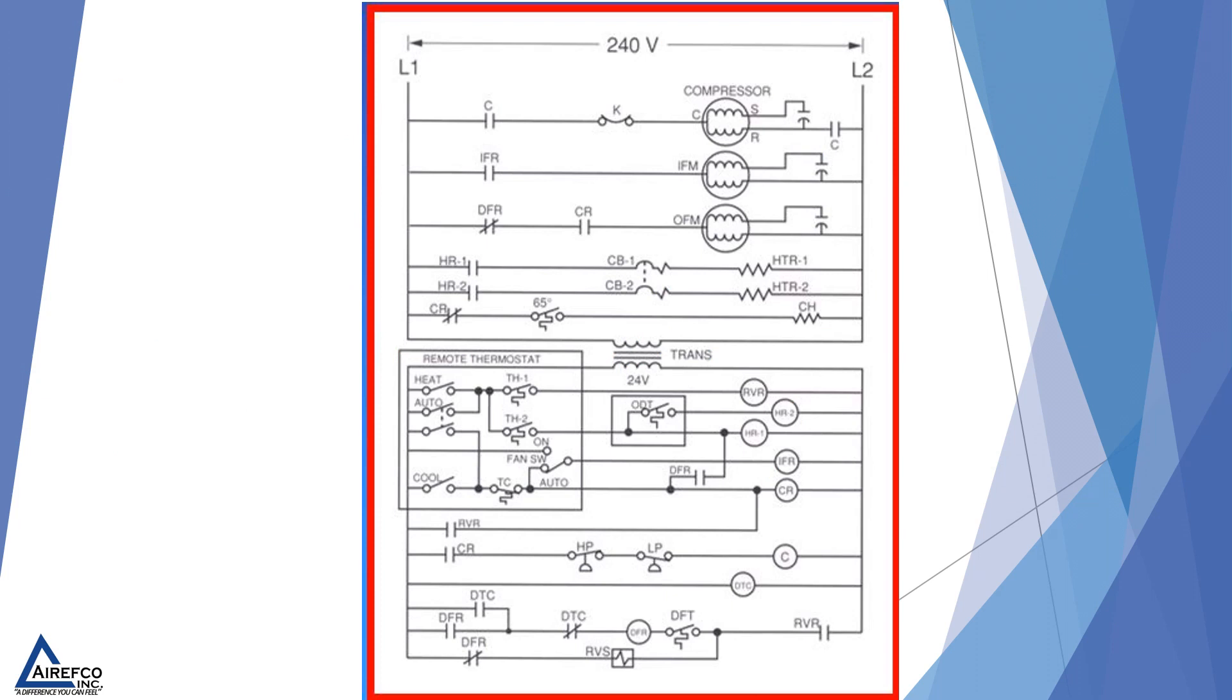This wiring diagram may look familiar to you, as it was on a recent NATE certification test. The question associated with this diagram was: when is the crankcase heater energized on this system? Here we find the symbol for crankcase heat, and we see that it is controlled by the CR relay. When the CR relay is open, which happens during the off cycle, the one contact of the CR relay closes.